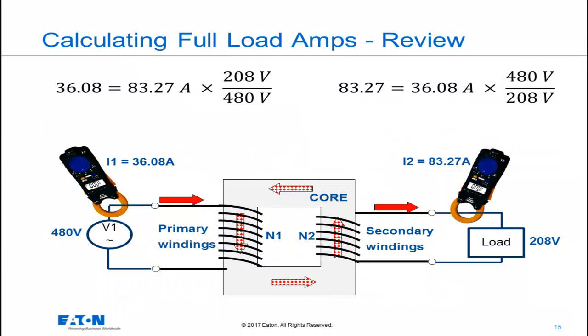So this is just a different way of looking at the exact same calculation we just made. If I'm drawing full load amps on the secondary and place a meter in that location, the meter would read 83.27 amps. If I placed a meter on the primary at the same time, the current on the primary would read 36.08 amps, thanks to the turns ratio of the transformer.